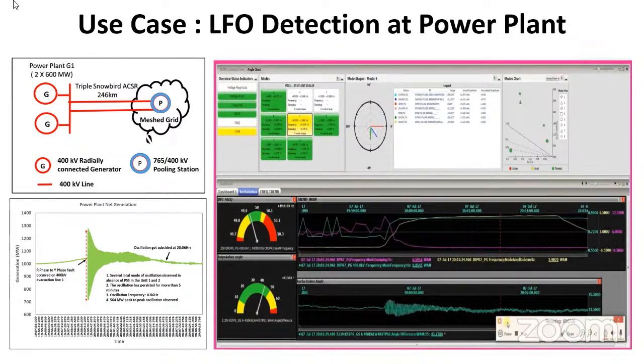One plot represents the frequency of the oscillation, and another shows the magnitude of that particular frequency mode. Both magnitude and frequency went up because it was an intraplant or interplant kind of oscillation, while the damping went down due to the PSS not being properly tuned.